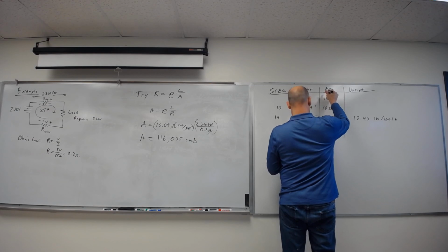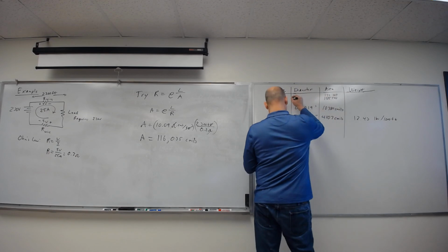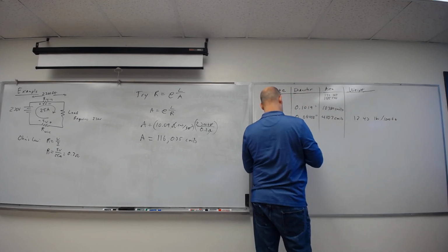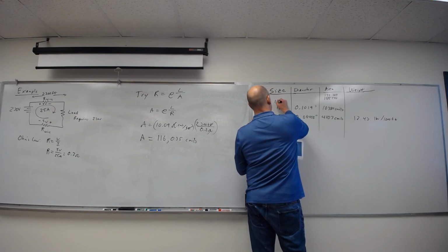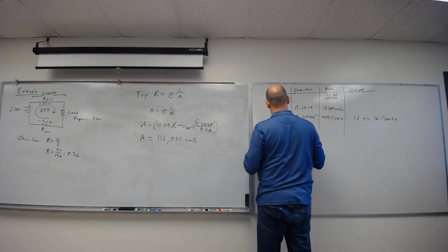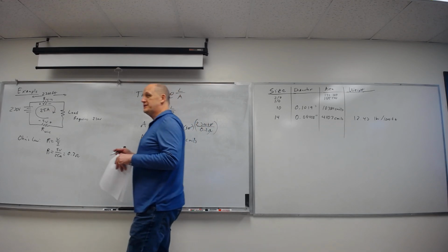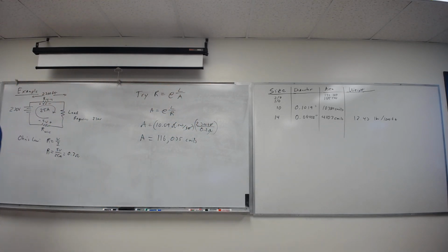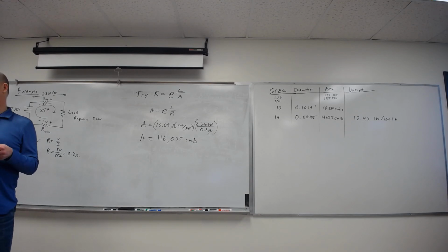105,500. The next one is 133,100. And I look over here. This is labeled 1/0. This is labeled 2/0. So I want the thicker one, so it's got a lower resistance. That means I actually need double-aught wire to carry that. I look way over to the side, double-aught wire weighs 400 pounds per 1,000 feet.